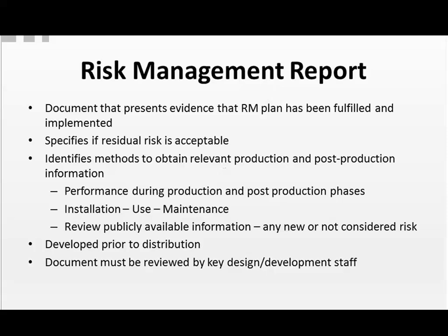It must explain the methods to obtain relevant production and post-production information, such as performance during production and post-production phases, installation, use, and maintenance. You need to review publicly available information to uncover any new or unconsidered risk. The document must be developed prior to the distribution of the device, and the document must be reviewed by key design and development staff.